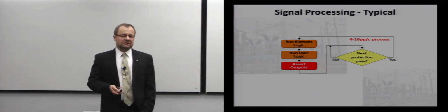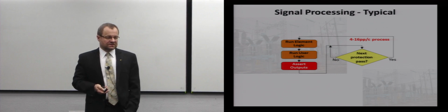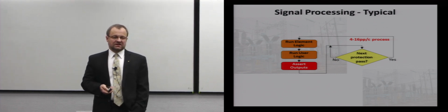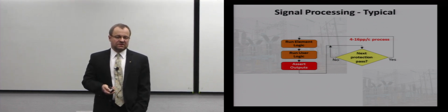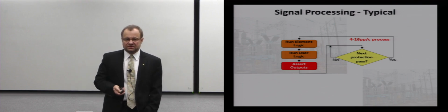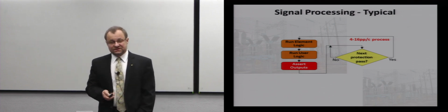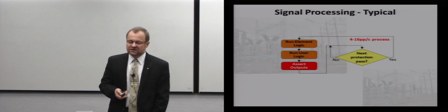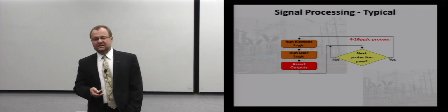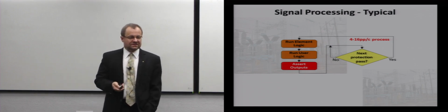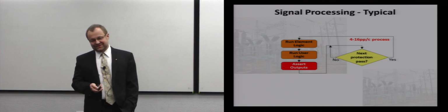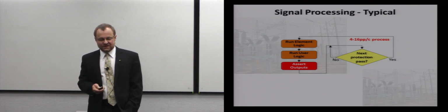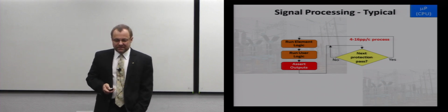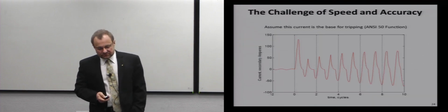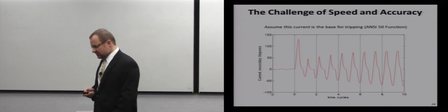That new relay that I showed you runs at 8 protection scans per cycle. So roughly every 2 milliseconds we decide whether we should close the contact or not. It samples at 8 kilohertz. And it does data crunching at 32 times a cycle. So it has all those 3 rates, right? So this is how you do it.